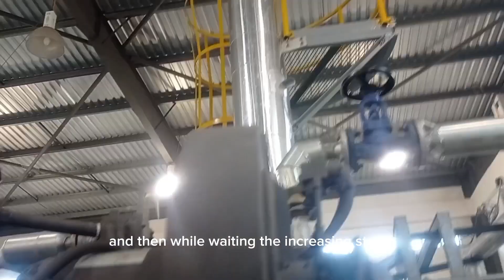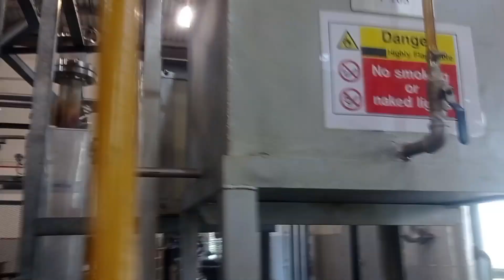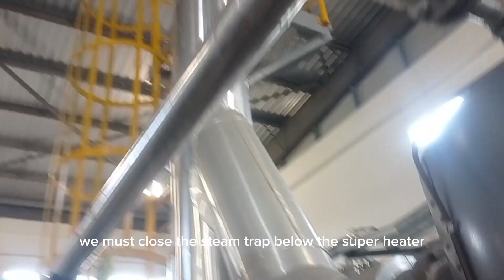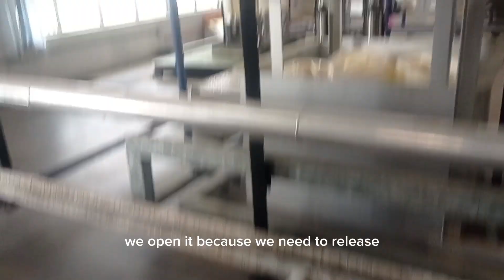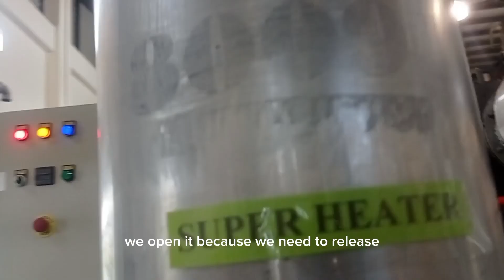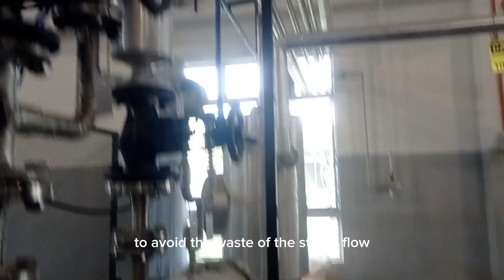And then while waiting for the steam to increase, we can open MV1 to 2, which is first opened to 5% to heat the pipeline, and then next open it to 10% until 100%, so the steam will go to the steam header, and when there is steam, we will see it at the drainage. When the steam is ready, we must close the steam trap below the superheater to avoid wasting steam. We open it because we need to release the condensed water in the pipeline, and then we close it again to avoid wasting the steam flow.